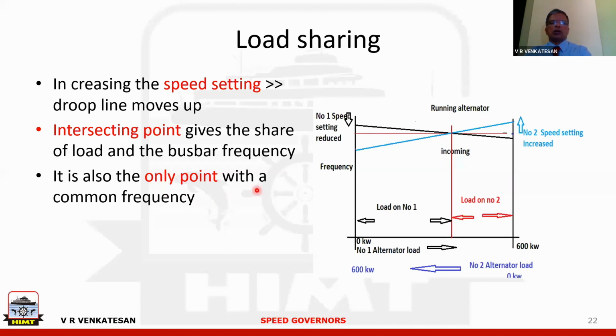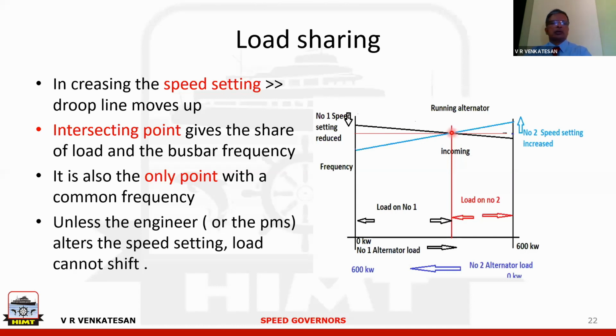This is also the only point with a common frequency. Because the important point is parallel running machines have to run with the same frequency. So where is the frequency constant or same in both of them? Can it be here anywhere? Intersecting point. The only point where the frequencies are same is the intersecting point. And this is the only point at which it will run. So the advantage of this is, unless the engineer or the power management system alters the speed setting.